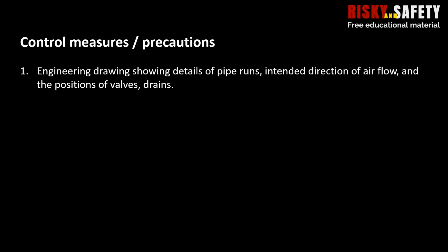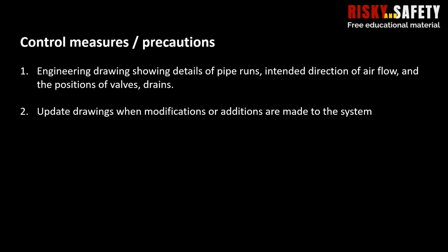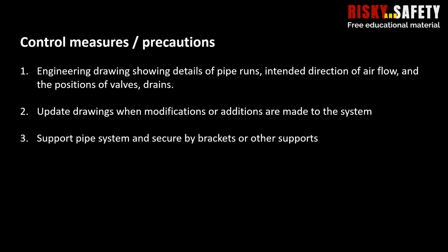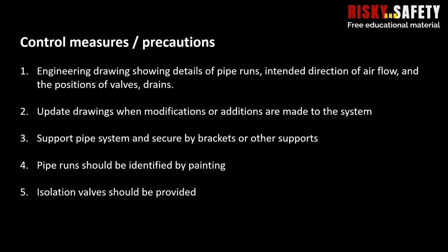You can control the risks by keeping air system engineering drawings showing details of pipe runs, the intended direction of air flow and the positions of valves and drains. Update drawings when modifications or additions are made to the system. Support the pipe system and secure it with brackets or other supports. Pipe runs should be identified by painting. Isolation valves should be provided. Provide a notice indicating the position and or purpose of the valve.